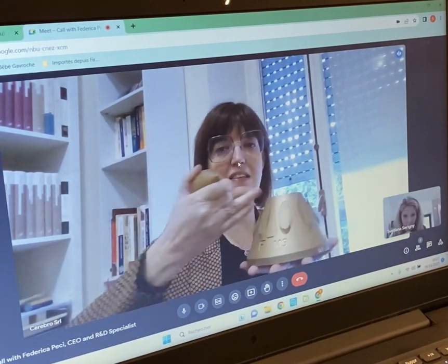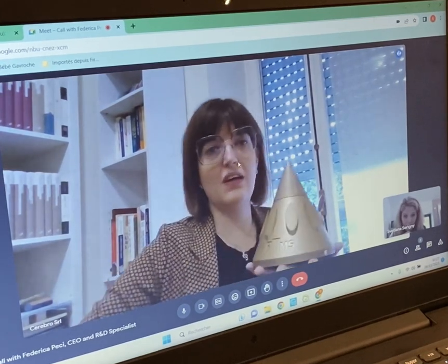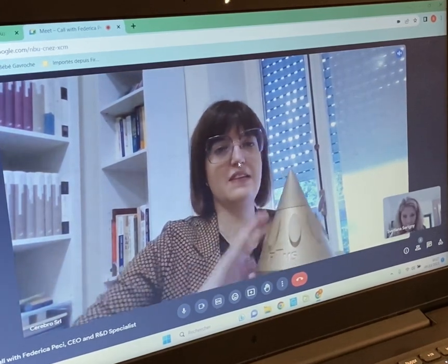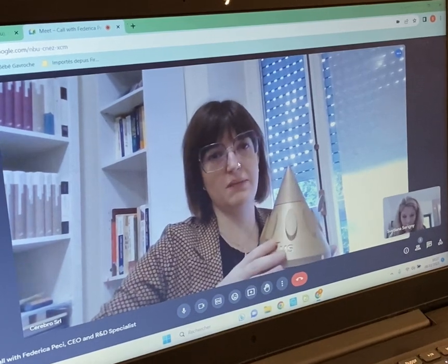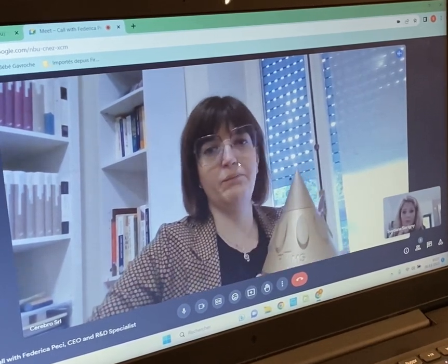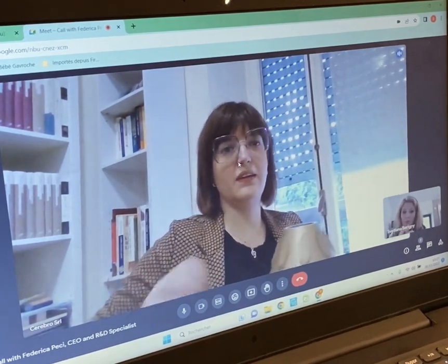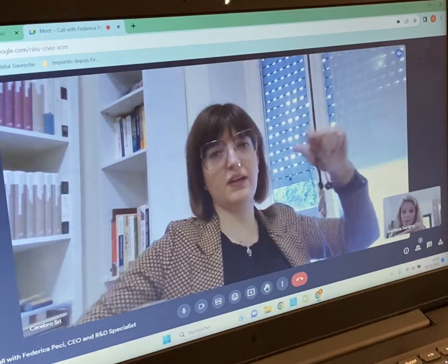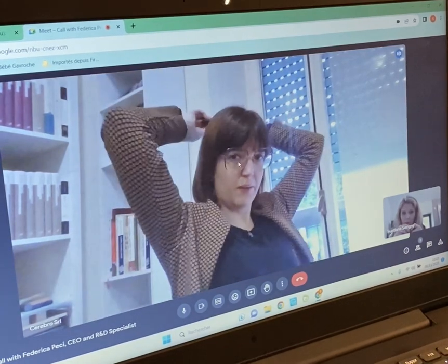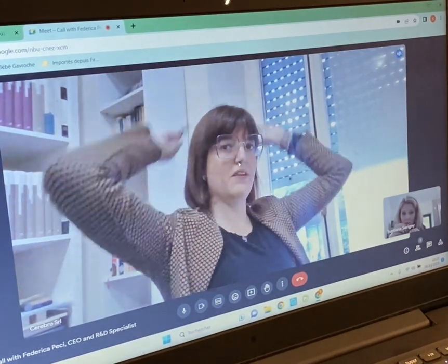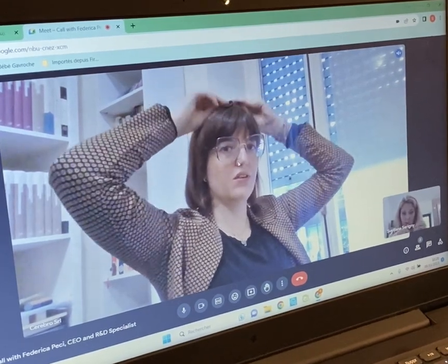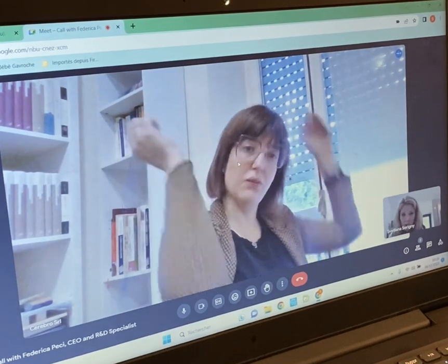So when I take the cone off, the magnetism is produced inside the machine, and if I place it over, then it stops the magnetism inside the device. So you can take the cone off, place the device inside the jetpack, and have the cables come from the back, so they are not interfering in the front with the reading.